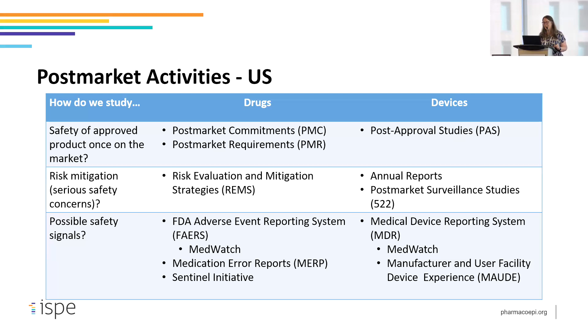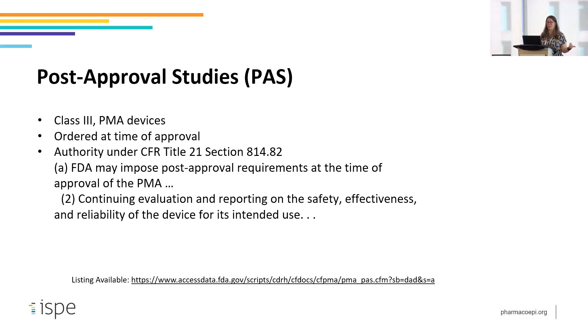For the safety signals themselves and the evaluation of the safety signals, there is a passive surveillance system. The medical device reporting system in the United States is called the Manufacturer and User Facility Device Experience, MAUDE. Worst acronym ever. So post-approval studies can only be required for those highest risk devices. There's very specific needs for them. It looks a lot like PMR and PMC for drugs. For 522s, they can only be asked for those mid-level risk and high-level risk devices.